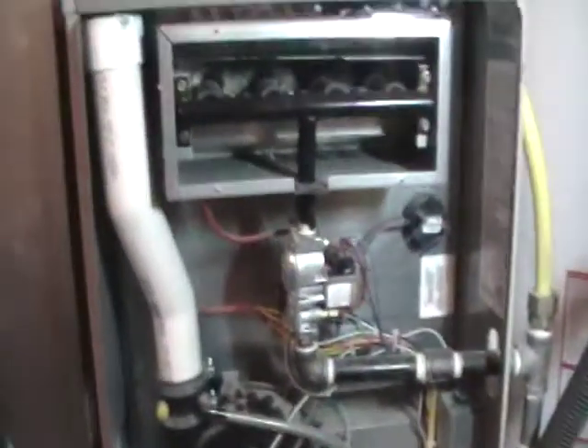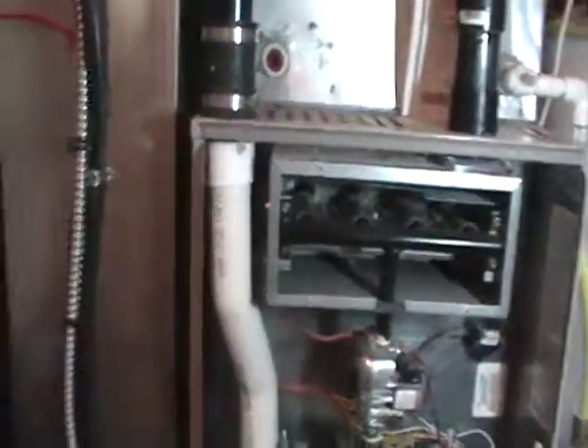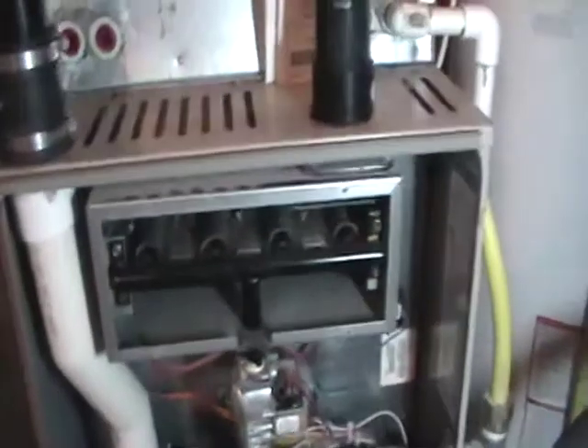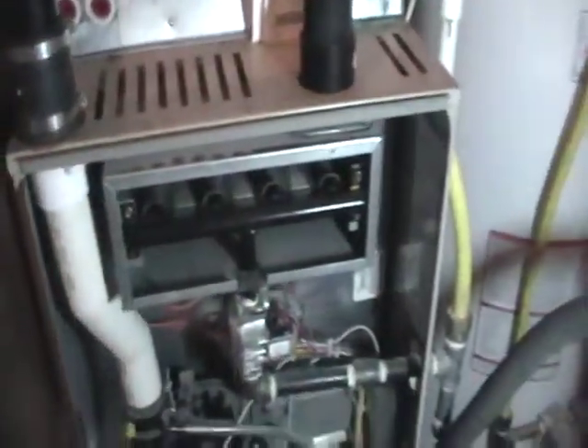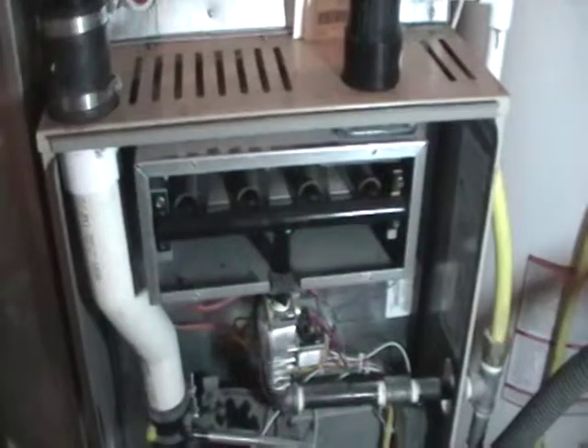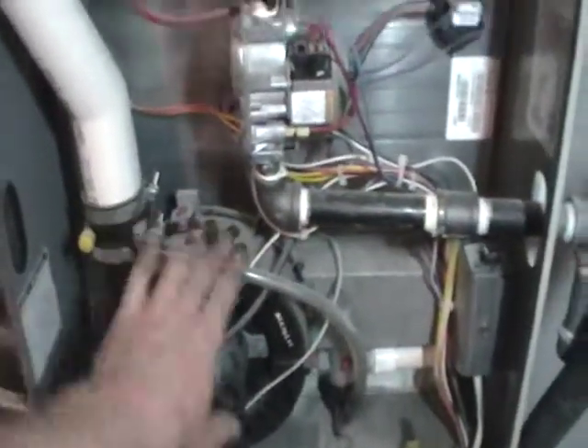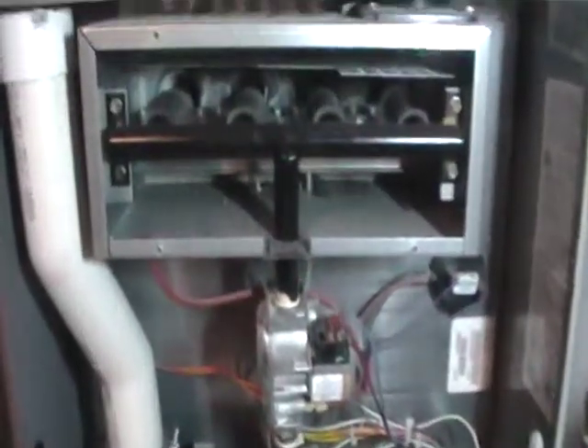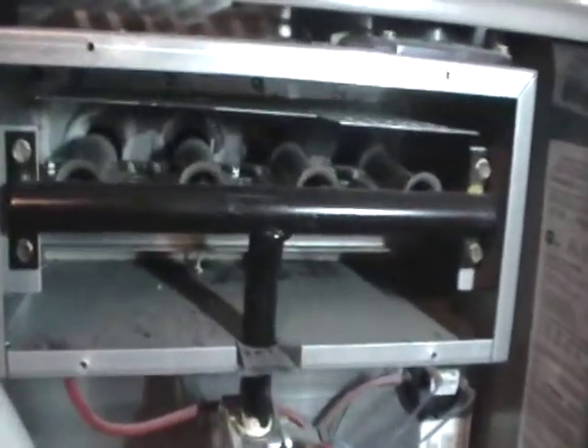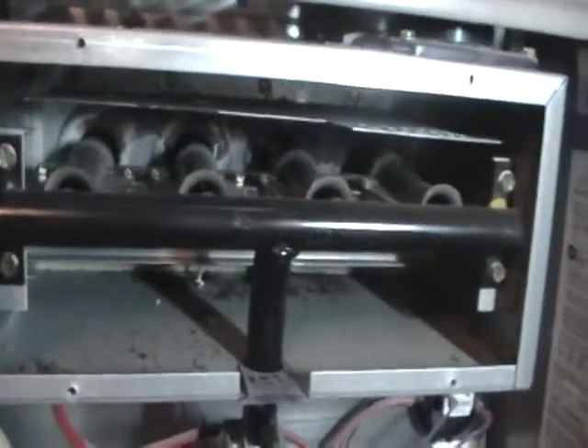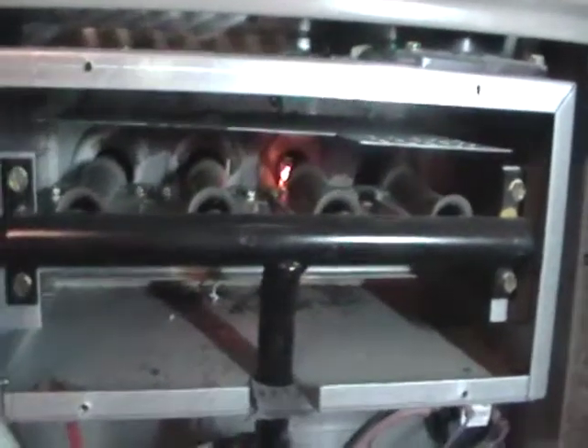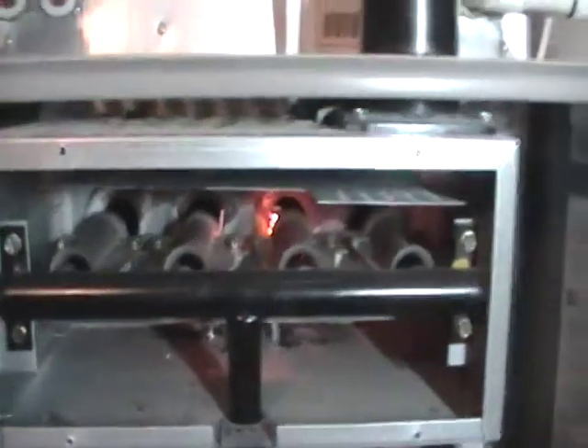Now, I've already pulled the cover off the combustion box on this one. You won't need to do that on your own furnace. You can generally just cycle it and look through the sight glass, but for the video it looks a little easier here. So let's watch the heating cycle. First, the venter motor is going to turn on, clears off any products of combustion in the combustion chamber. Next, the hot surface igniter is going to start to glow. As that hot surface igniter starts to glow, the gas valve is going to open, give gas to the manifold, and it's proven across onto the flame rod, which is right there.